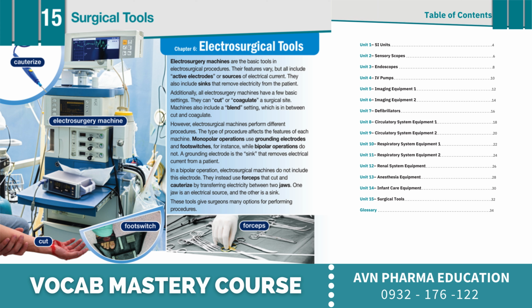However, electrosurgical machines perform different procedures. The type of procedure affects the features of each machine. Monopolar operations use grounding electrodes and foot switches, for instance, while bipolar operations do not. A grounding electrode is the sink that removes electrical current from a patient. In a bipolar operation, electrosurgical machines do not include this electrode. They instead use forceps that cut and cauterize by transferring electricity between 2 jaws. One jaw is an electrical source and the other is a sink. These tools give surgeons many options for performing procedures.